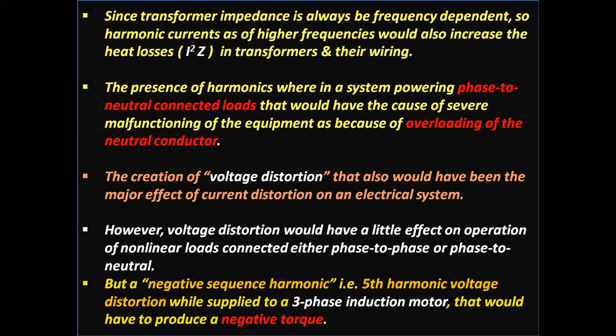Since transformer impedance is always frequency dependent, harmonic currents at higher frequencies increase heat losses — that is I²Z, where Z is the impedance — in transformers and their wiring. The presence of harmonics in a system powering phase-to-neutral connected loads can cause severe malfunctioning of equipment due to overloading of the neutral conductor.